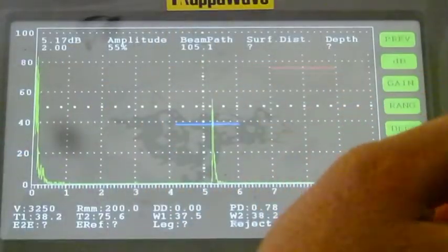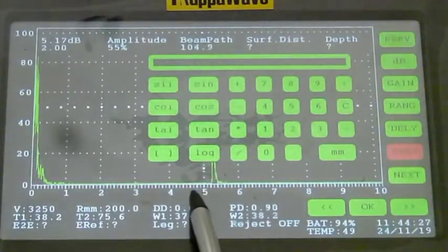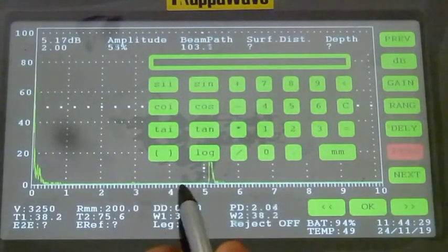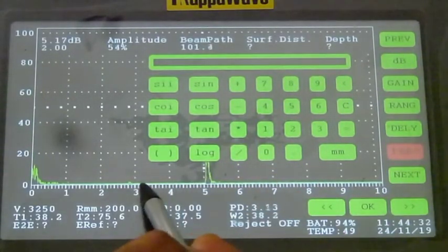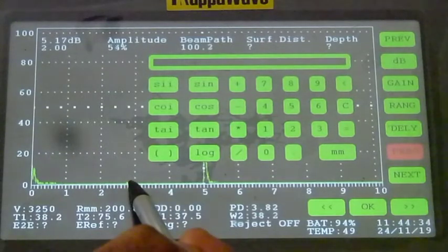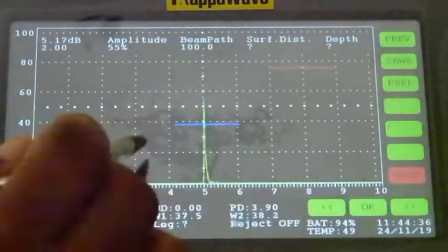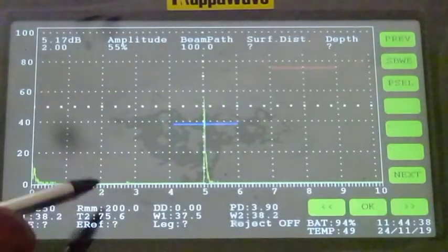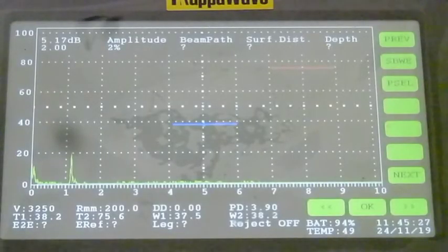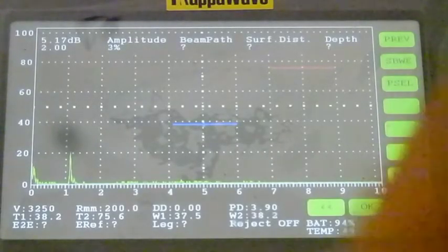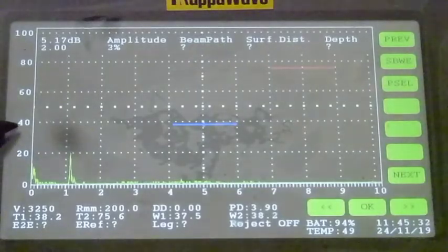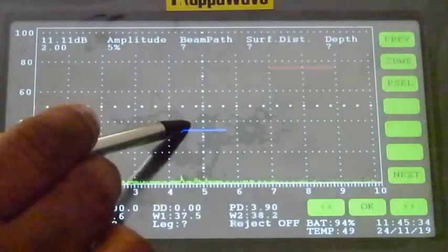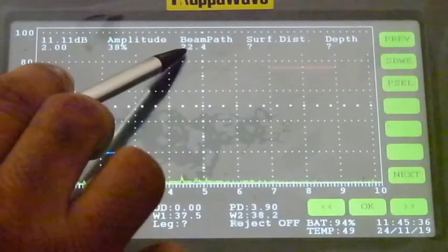This instrument also has an AWS D1.1 weld testing tool. After calibrating to something like 200 millimeter using a V1 block, a 45-degree probe is being used in this case, placed on a V1 block to pick up a 1.5 mm diameter side drilled hole, and then set this echo to about 40% in height, and then engage the AWS function.